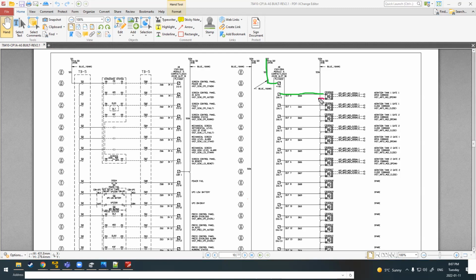A1 and A2 are wired up. So you have your 24 volts into A1, A2, that's your coil in the relay, comes out, goes back up to 0 VDC. Your 0 VDC will be run common down these relays. So when the relay coil pulls in, it closes your contacts and this gate valve will start to open.